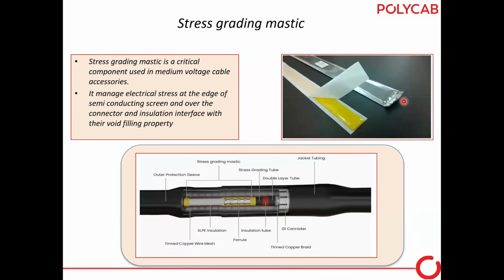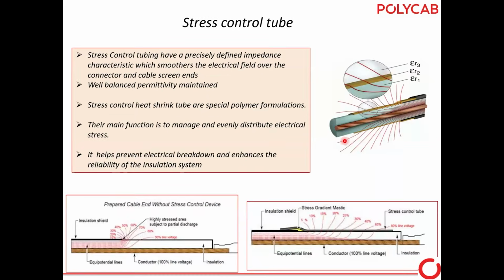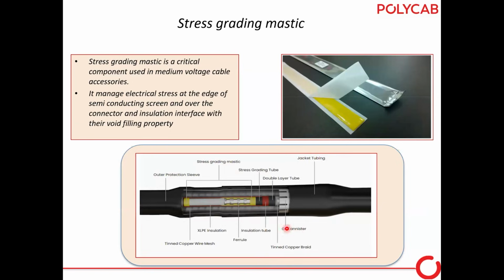Then we require stress grading mastic. Wherever we cannot use a tube, like in the last slide here in the step, because air always forms here, at this point we use the tape. Likewise, this stress grading mastic is used. So this is a very critical component again. It manages electrical stresses at the edge of the semiconducting screen, like here, and over the insulation.